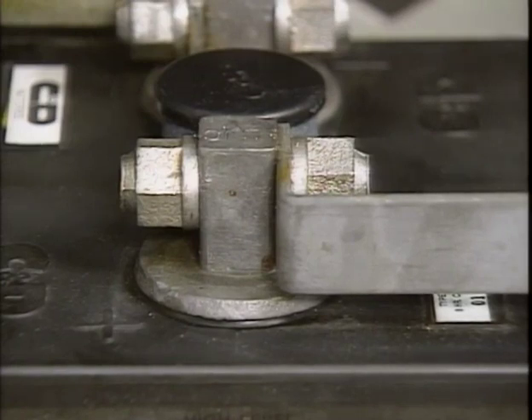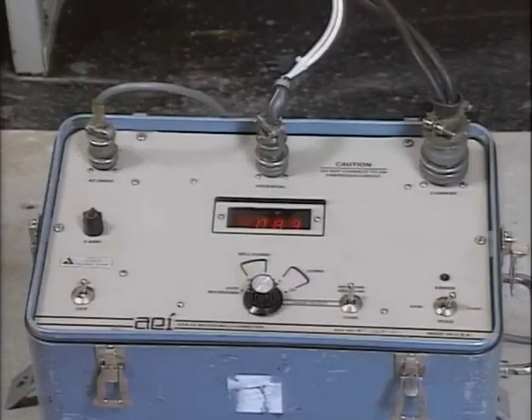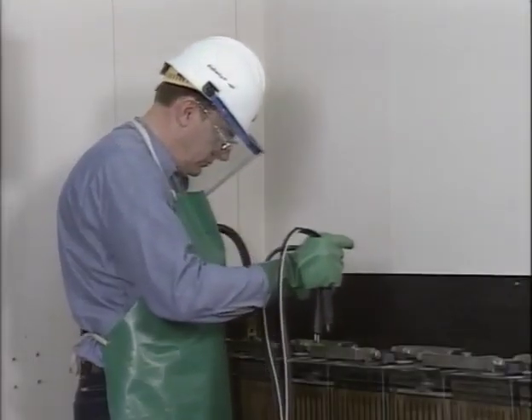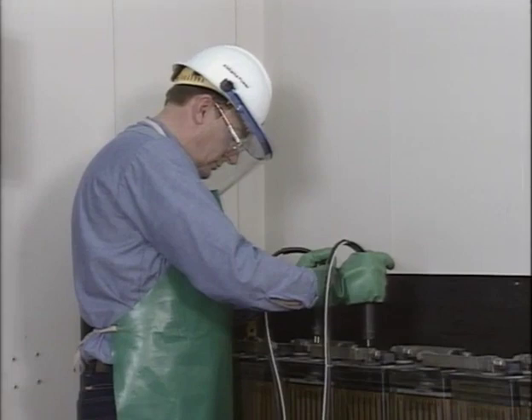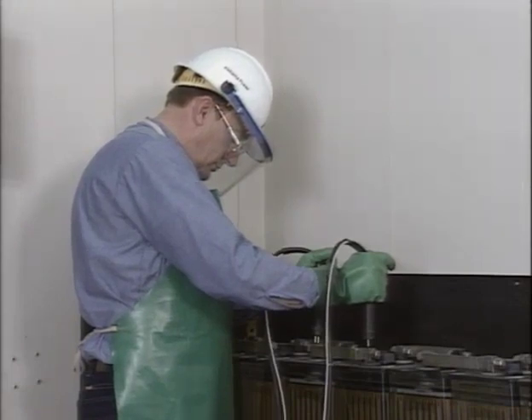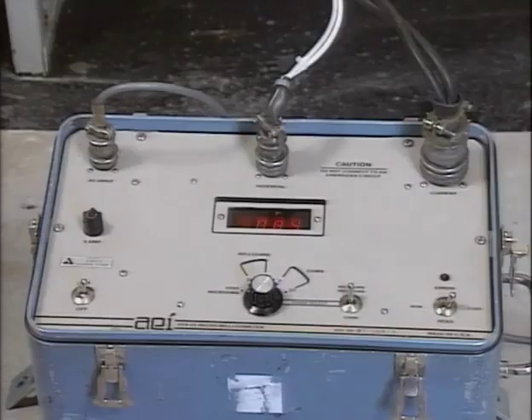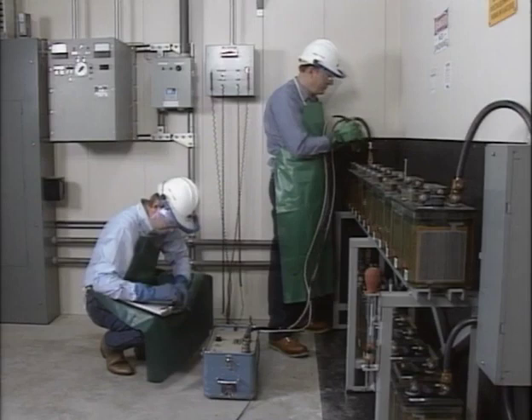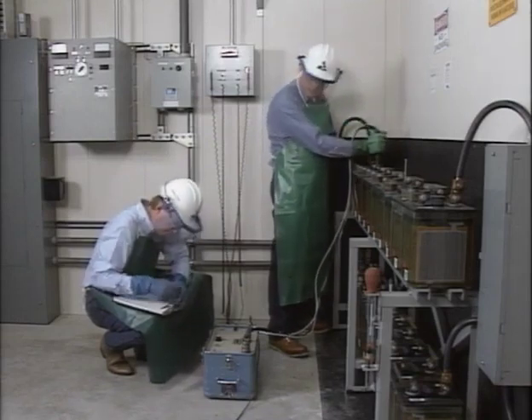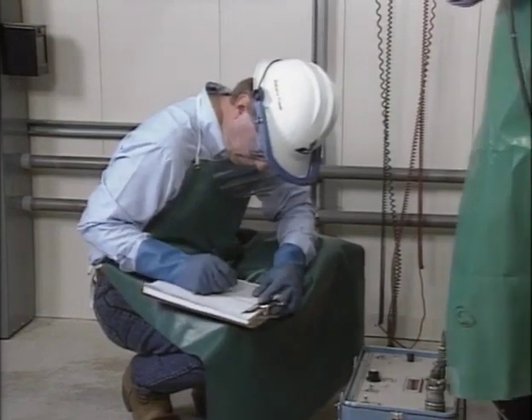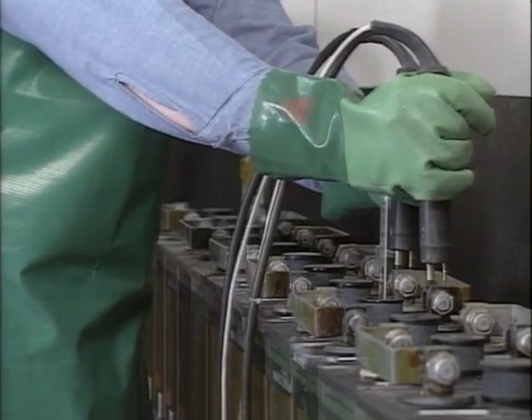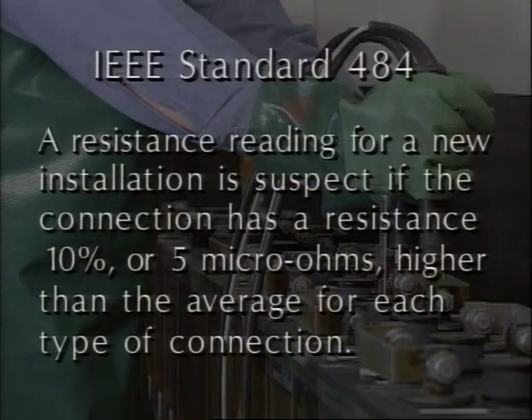One way to check the connection is with resistance testing. Connection resistance is commonly measured using a micro-ohm meter. A recommended practice is to connect one probe of the micro-ohm meter to the positive terminal of a cell and the other probe to the negative terminal of the adjacent cell. This micro-ohm meter applies a 25 amp test current across the intercell connector and electronically calculates the resistance. It's a good practice to start taking resistance readings at one end of the battery and work toward the other end. Each micro-ohm resistance reading is recorded. Normal resistances can vary with the size of the battery. According to IEEE Standard 484, a resistance reading for a new installation is suspect if the connection has a resistance that's 10% or 5 microohms higher than the average resistance for each type of connection.